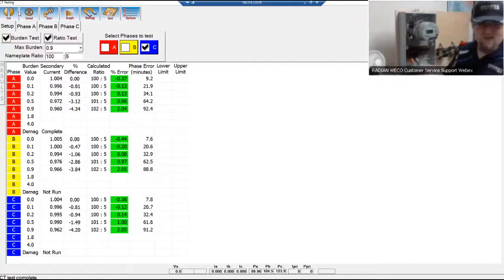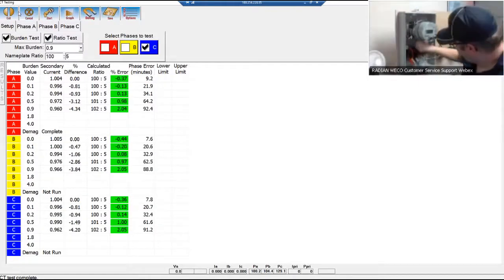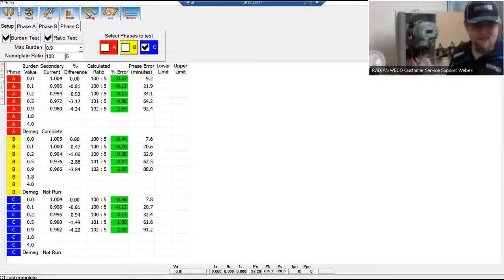So because we have our A-phase and neutral alligator clips, same thing, we're going to clip up to the test switch on our A-phase and neutral to get the Bantam in line with voltage at the site. And then our one duckbill, we're going to put on the phase we want to measure. So in this case, same idea. I'm going to go ahead and short out the CT secondary, deaden everything on this side, open up our test switch, red side up. I'm going to plug in the duckbill. If you push too hard, you can pull back just a little bit to not short out the back end. Close that up, and now we're in line on A-phase.